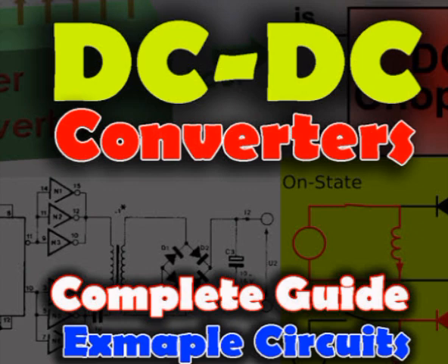If you want four quadrant application, you need to have two converters connected in anti-parallel position. Again, I repeat, if you want a converter to work in all four quadrants, you need two converters connected in anti-parallel position, as you can see in figure 1b. This can happen without any mechanical changeover switch.